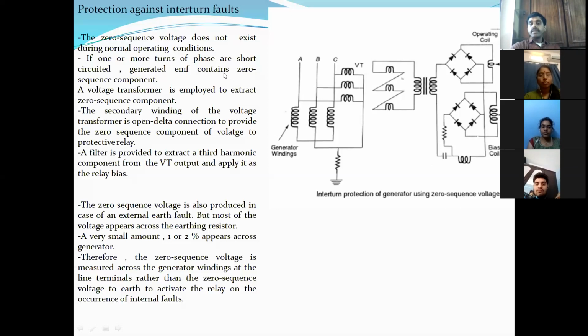That zero sequence voltage will be taken as a sensing parameter to protect the generator against interturn faults. If one or more turns of the phase are short circuited, the generator EMF contains a zero sequence component. So zero sequence voltage will be existing. That zero sequence voltage we have to extract, and that should be given to the operating coil for the relay to operate. A voltage transformer is employed. Here you can see a voltage transformer is employed to extract the zero sequence component.